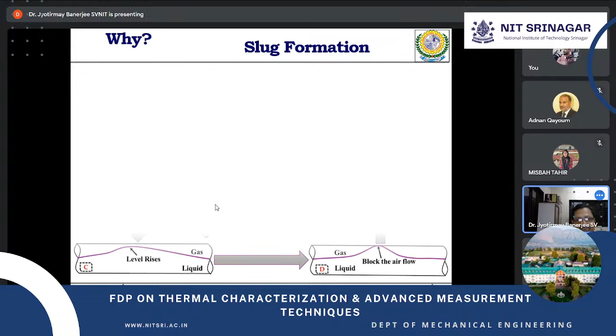When superheated steam comes out of the boiler and starts flowing through the pipe, because of the heat loss from the pipe wall, a part of the steam gets condensed and a part remains in the gaseous phase. So a part becomes liquid and another part stays gaseous. In the most common scenario, there will be a liquid and gas separated by a sharp interface. The liquid will be flowing below and the gas will be flowing above.